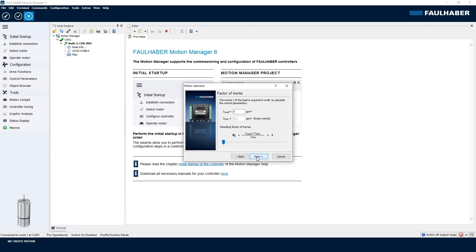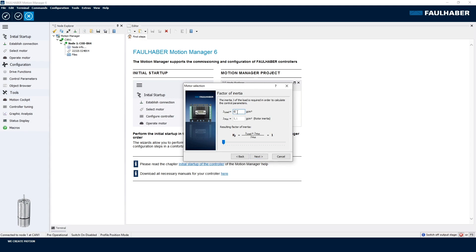The last one here is to give an estimate for the actual inertia that is hooked up to the motor, because the inertia is the dominating factor for the selection of the gains for the position loop and for the speed loop. In that case here, second generation of our drivers, there is no auto-identification of the inertia, so I have to guess.